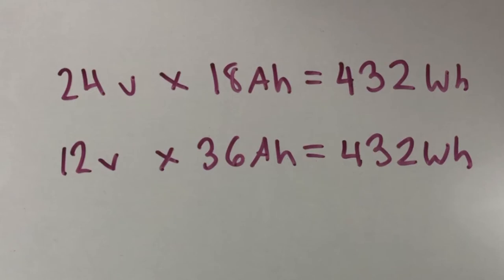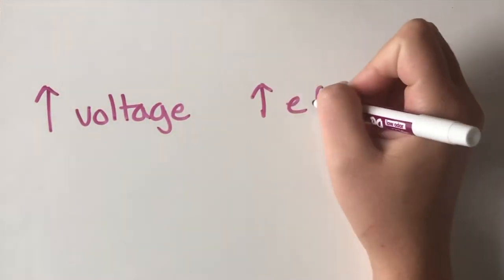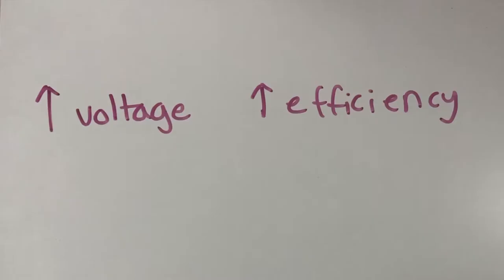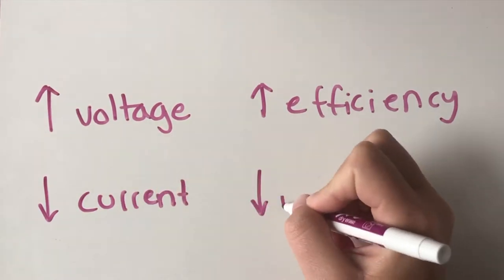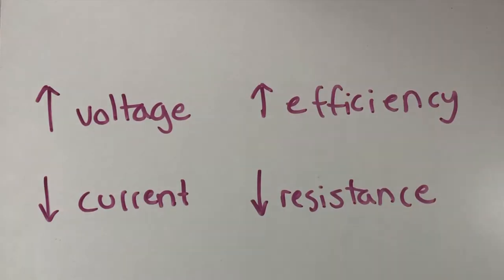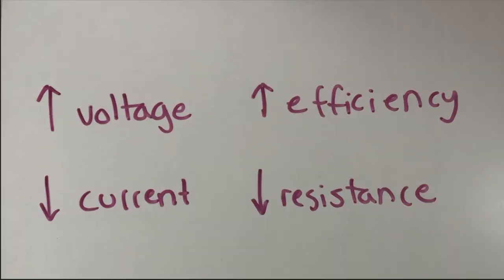So you might be wondering, if the watt-hour is the same, what's the point in wiring the batteries in series over parallel? Higher voltage increases the efficiency. This also results in a lower current, which lowers the resistance losses in the conductors. Low resistance means lower the energy loss.